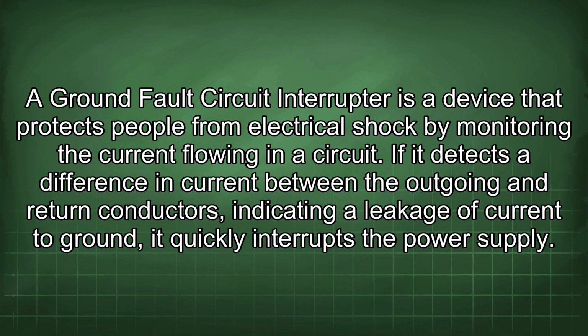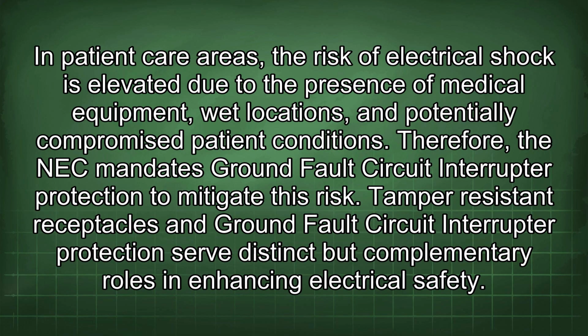hospitals. A ground fault circuit interrupter is a device that protects people from electrical shock by monitoring the current flowing in a circuit. If it detects a difference in current between the outgoing and return conductors, indicating a leakage of current to ground, it quickly interrupts the power supply. In patient care areas, the risk of electrical shock is elevated due to the presence of medical equipment, wet locations, and potentially compromised patient conditions. Therefore, the NEC mandates ground fault circuit interrupter protection to mitigate this risk.